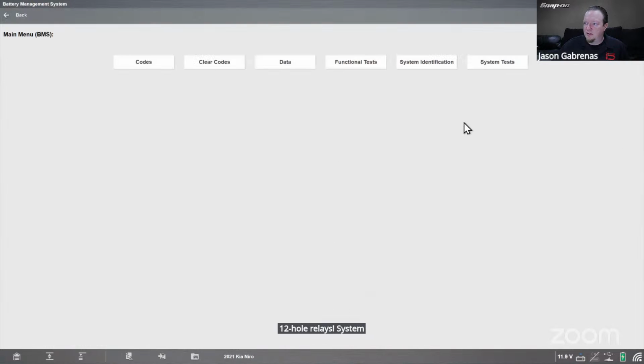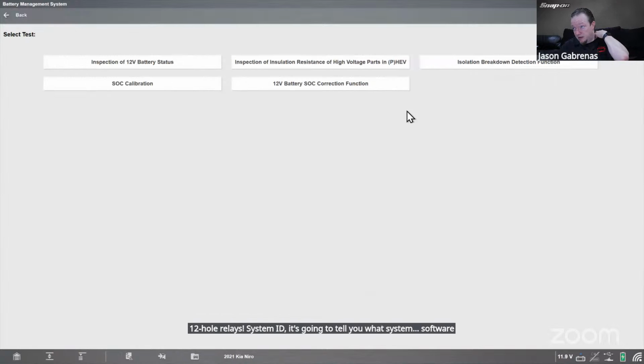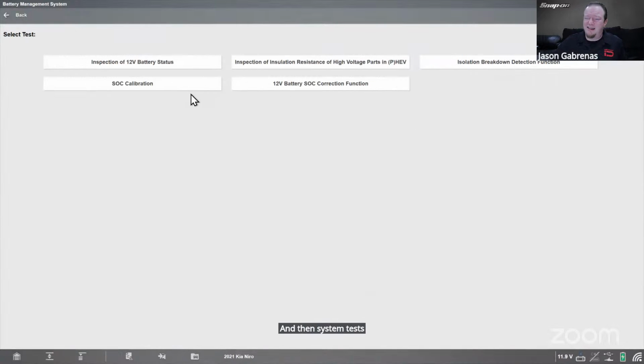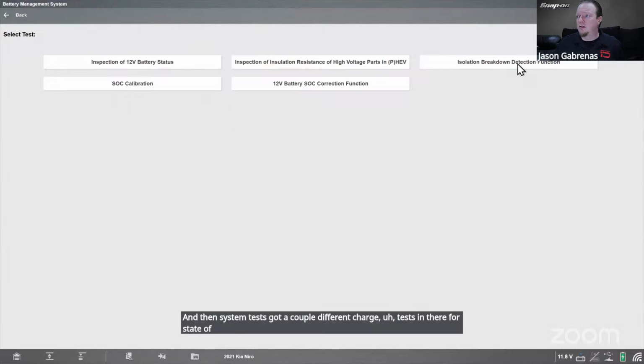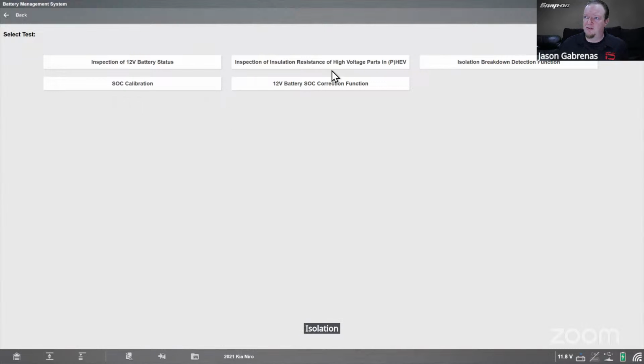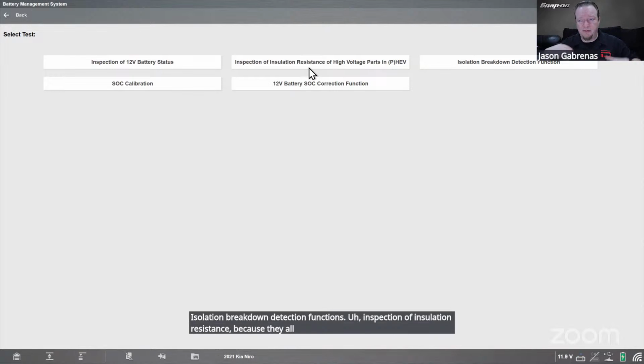It's going to tell you what system software version it's running. Then system tests, with a couple different charge tests for state of charge calibration, isolation breakdown detection functions, and inspection of insulation resistance, because they all have to be isolated from each other in the pack. Also a couple tests for the 12-volt battery.